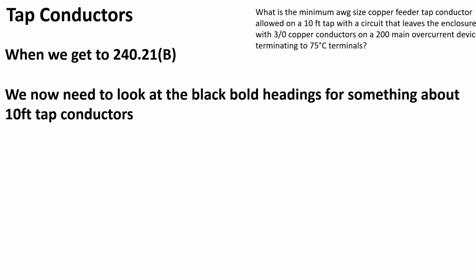So the ampacity of the tap conductor is (A) not less than the combined calculated load on the circuit supplied by the tap conductor. So if you know that you're tapping this conductor for a 30 amp motor, regardless of all these other codes, the wire has to be sized for the 30 amp motor. Okay, part (B) says not less than the rating of the equipment containing an overcurrent device supplied by the tap conductor. So by the rating of the equipment. Part 2 says the tap conductor does not extend beyond the switch or panelboard. Part 3 says except at the point of the connection to the feeder, the tap conductors are enclosed in a raceway or a switchboard or panelboard or control device.